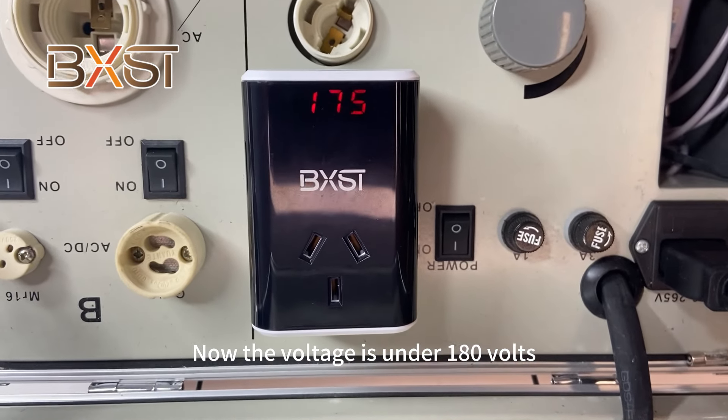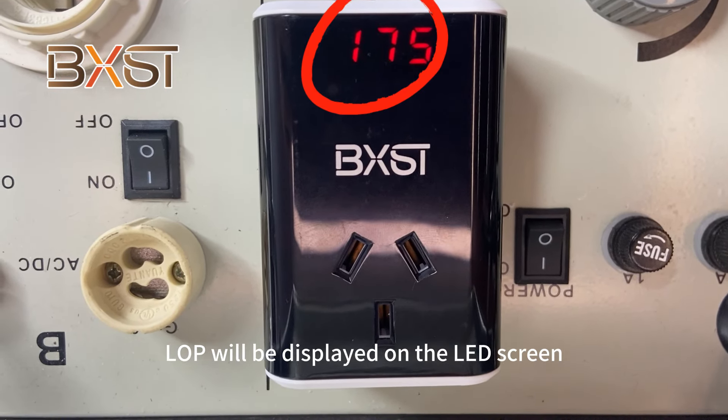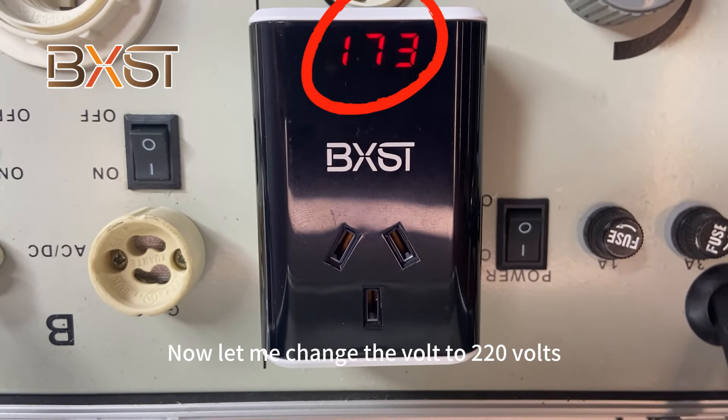The voltage is now at the low voltage level, around 175 volts, and our voltage protector is active. The rate of the value remains the same, meaning the voltage is being monitored across both the motor and the load.